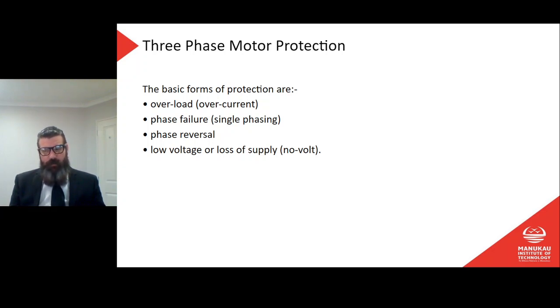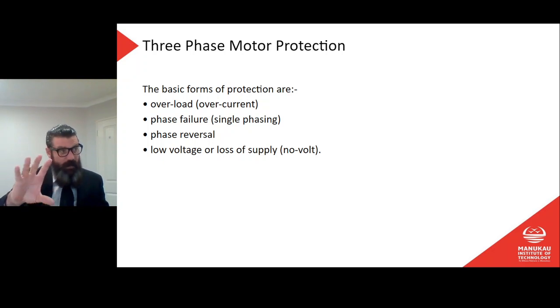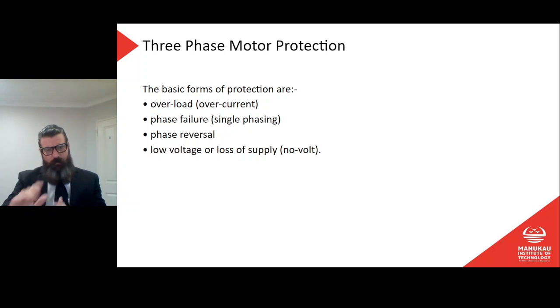Why? Because once the power goes off, everything stops. And again, let's say we're talking about that imaginary milling operation where I have big logs getting dragged everywhere. If the power goes off, okay, well, we have to stop. The last thing I want is for everything to restart by itself when that power goes back on, because there's a very high likelihood that things are going to start getting flung all over the place, and that's not what we want. So we need some sort of no volt protection, which means that when the power comes back on, I still physically have to go and reset that machine, motor, whatever it is. I've got to turn it back on before it'll restart.